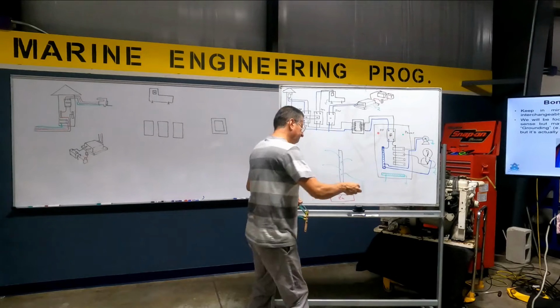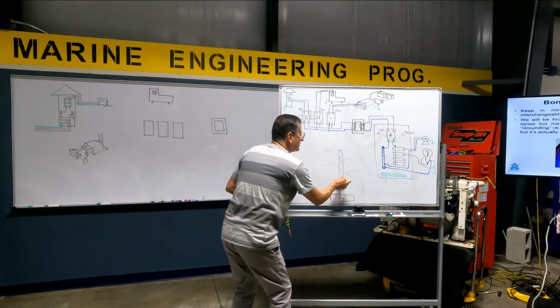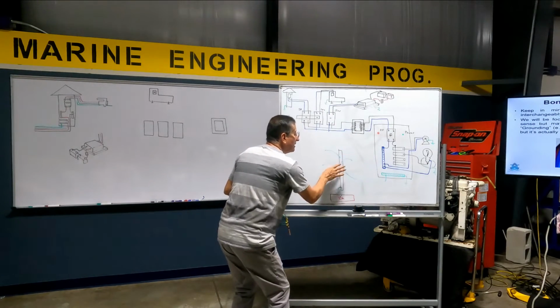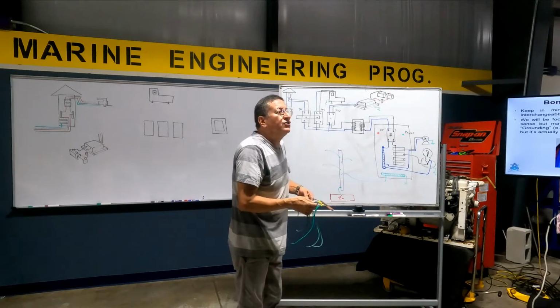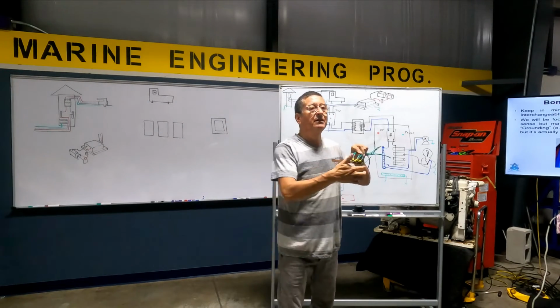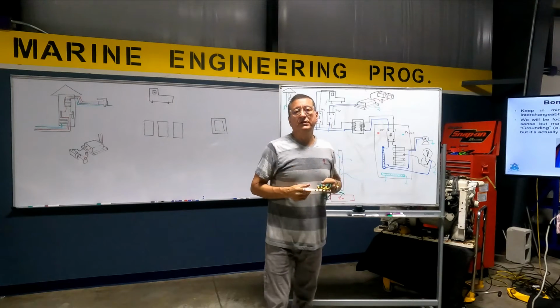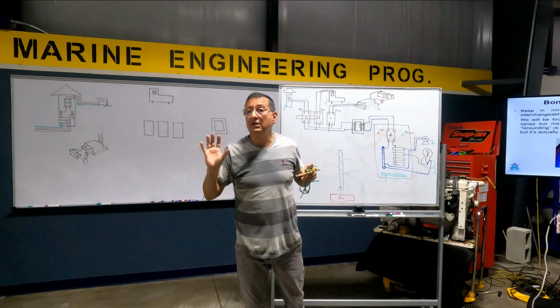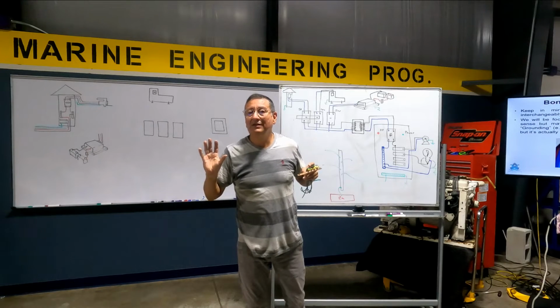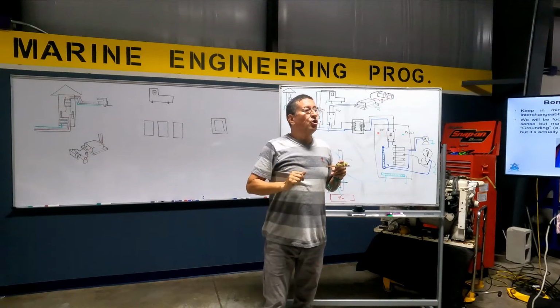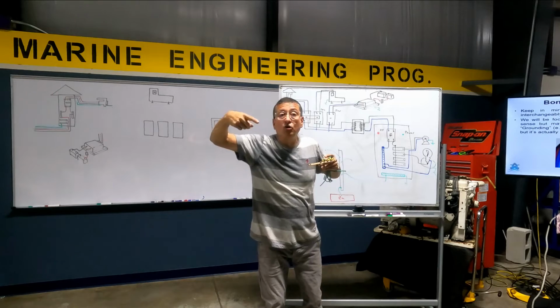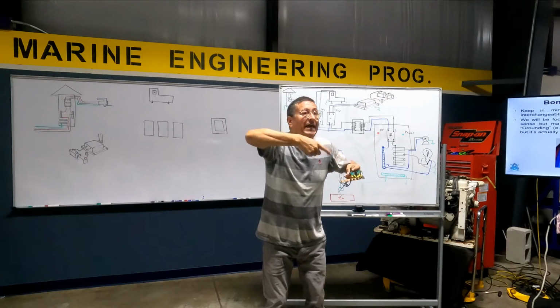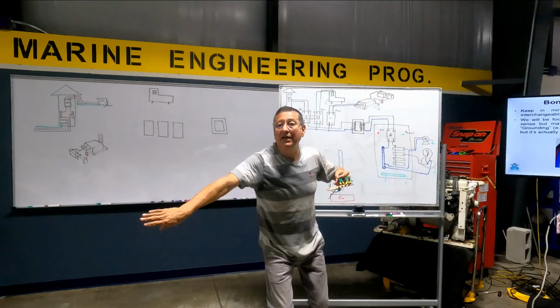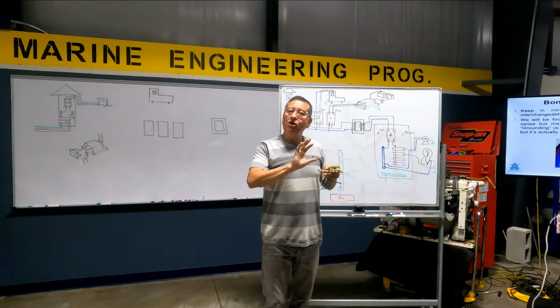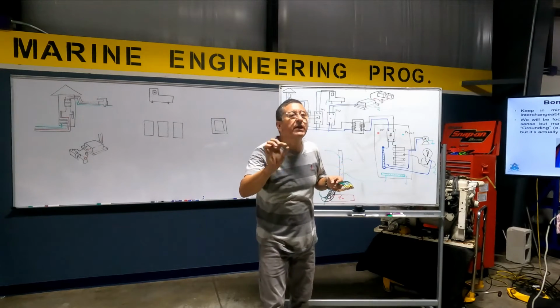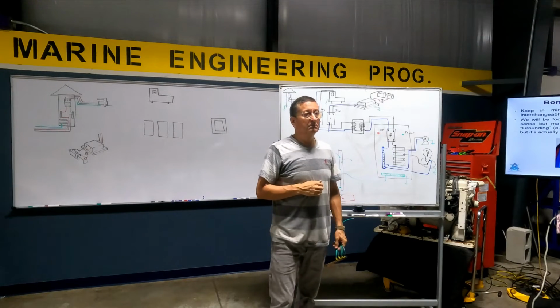What is the function of this grounding connection? To drain what? To drain static electricity, and in some emergencies, drain big currents — during a storm, lightning, or if a hot line in a motor is touching the case of equipment, it drains directly into the ground. But normally, in normal conditions, it's only draining small DC currents.